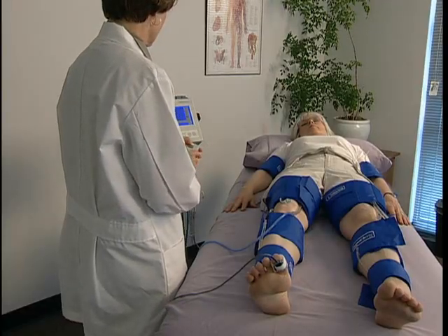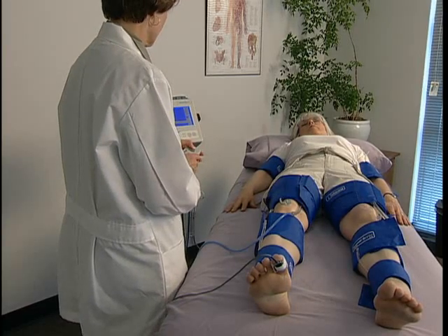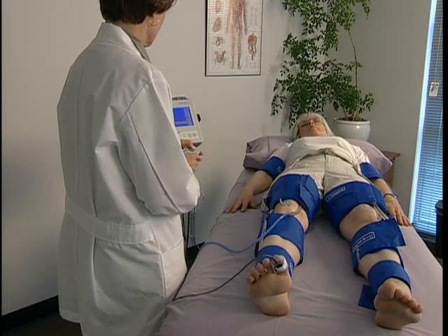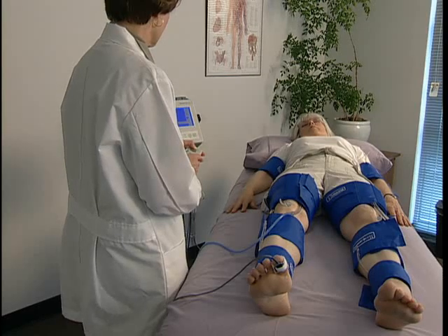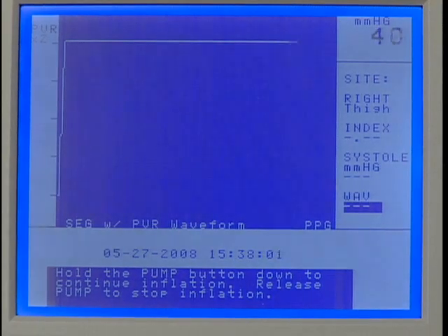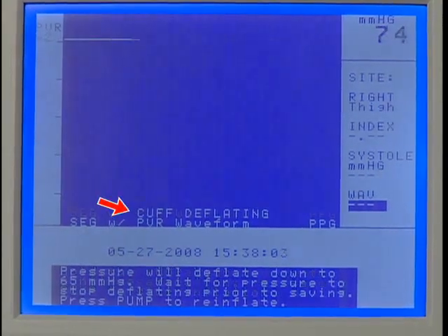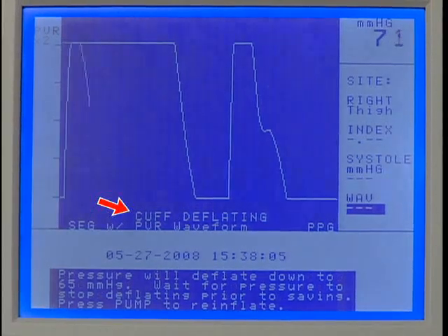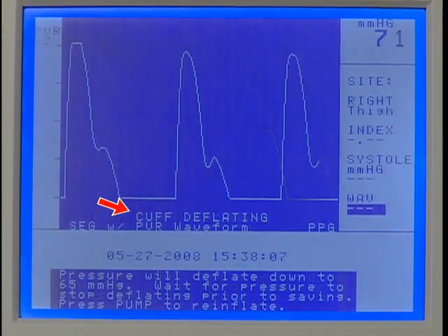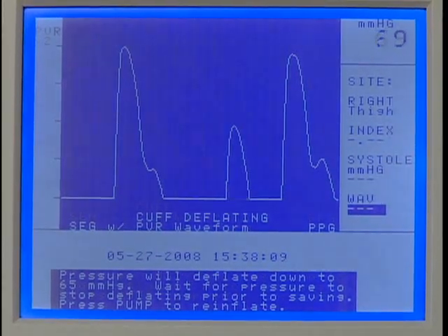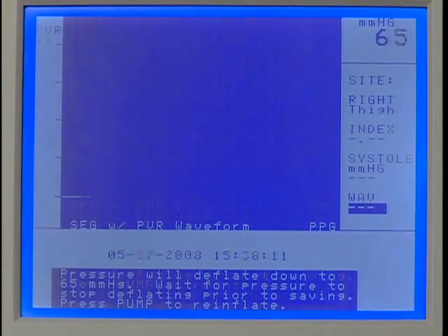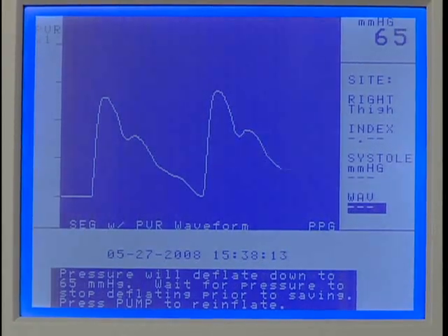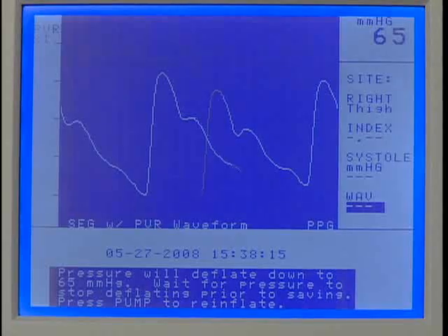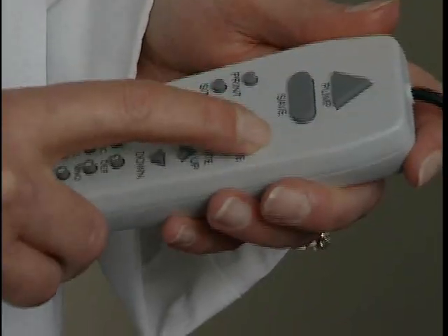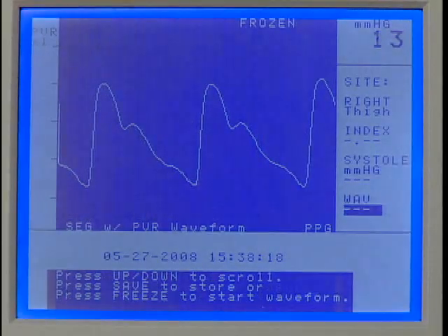Now we'll obtain a PVR ankle waveform. Press and hold Pump to inflate the cuff to 75 millimeters of mercury. Release when the inflation automatically stops. Pressure will deflate to 65 millimeters of mercury for optimum PVR. Wait for the cuff deflating message on the display to disappear. If needed, use the scale key to optimize the waveform. After the waveform stabilizes, press Freeze.